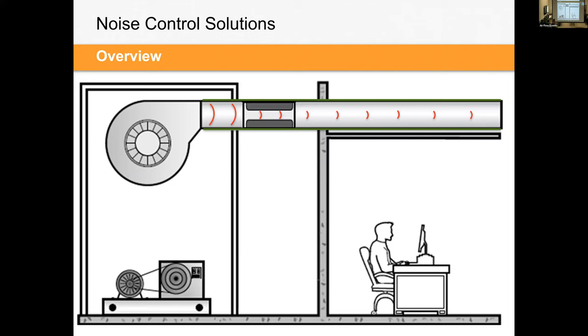Yeah, we've seen that quite a bit, where it's actually penetrating the wall or located in the wall itself. Is there benefit in that? There's no real benefit to that, is there? Not really. Except you've got half the silencer out where you don't want it to be, unless you cap it right at the wall. Yeah. But then you probably have a life safety challenge because you should have a life safety damper there. Yeah.